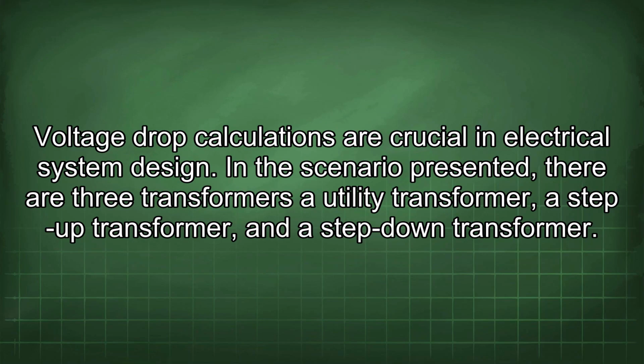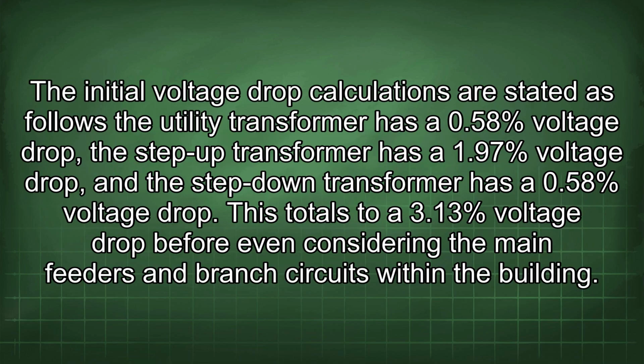Voltage drop calculations are crucial in electrical system design. In the scenario presented, there are three transformers: a utility transformer, a step-up transformer, and a step-down transformer. The initial voltage drop calculations are stated as follows. The utility transformer has a 0.58% voltage drop, the step-up transformer has a 1.97% voltage drop, and the step-down transformer has a 0.58% voltage drop. This totals to a 3.13% voltage drop before even considering the main feeders and branch circuits within the building.